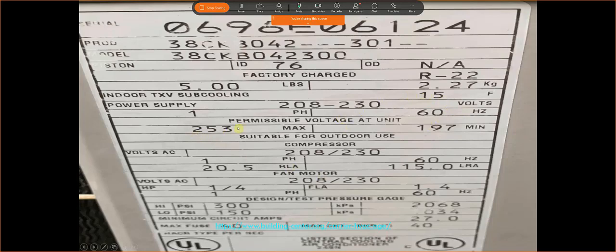The max voltage, 253. The minimum voltage, 197. And it's telling us it can be put outside. I hope so. And then volts AC for the compressor. The compressor is also running on 208, 230, single phase. My run load amps is 20.5 amps, 60 hertz, 115 lock rotor. So if my compressor were to seize up and I were to take my amp measurement, I would read 115 amps. At that point, I know my compressor is shot and I would need to put a brand new compressor in.